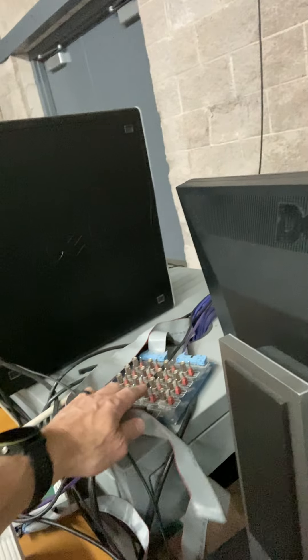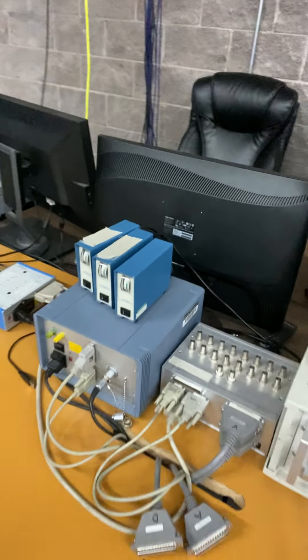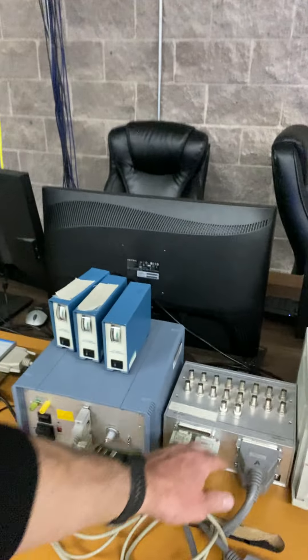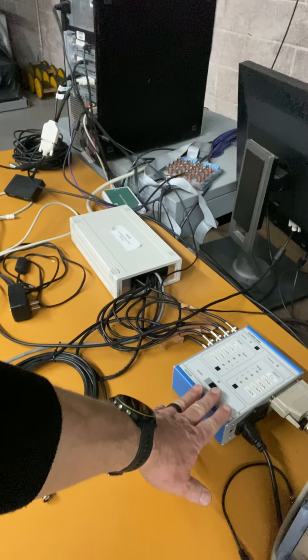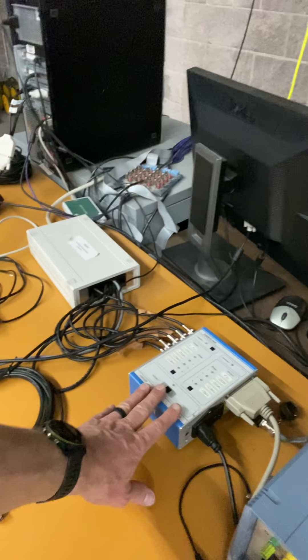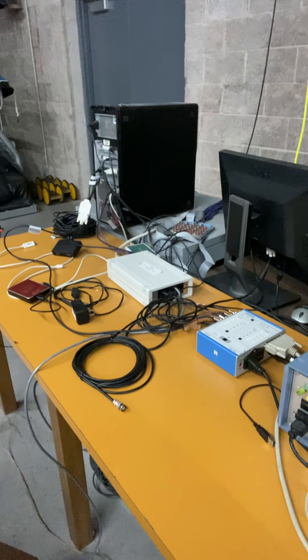This is another junction box — this one is from the Noraxon system. This is the switch that rectifies or keeps the data as raw. A little warning: if you use that, know that switch has to be flipped one way or the other. So the signal path is: amplifier, junction box, A-to-D board. This amplifier can also go to the other junction box, so we can record two force platform datasets in our A-to-D board, or this force platform goes to the Vicon junction box and off to the A-to-D board over there. That's the anatomy of a force platform.